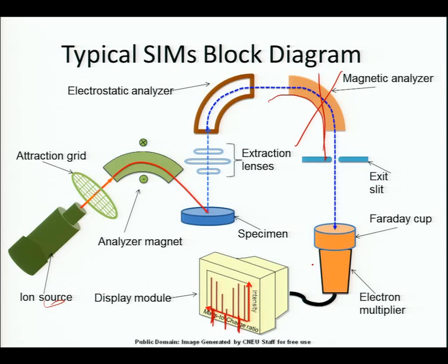Then we'll change the magnetic analyzer again to get our new reading, our new ion count. And then we'll count those ions for the same amount of time. Then we'll move to the next magnetic analyzer, change the magnetic flux on the magnetic analyzer to select a different ion.